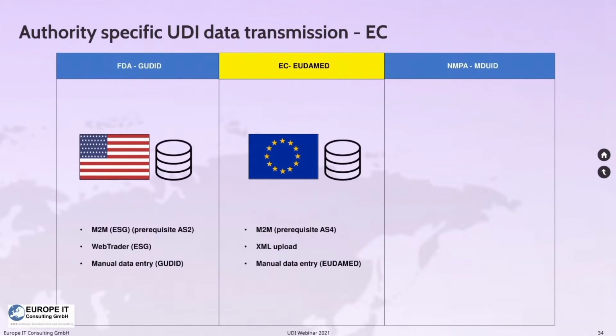For the European Commission and the EUDAMED database, the data can be transferred also via M2M, machine-to-machine, but this requires, other than in the GUDID, an AS4 protocol. And using the web interface, the data can also be entered manually.